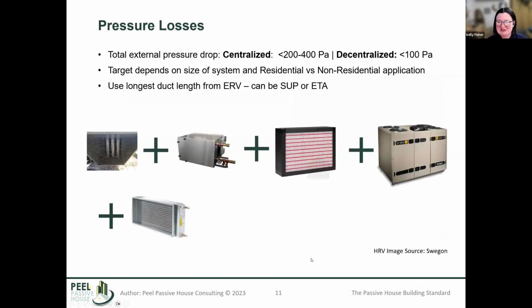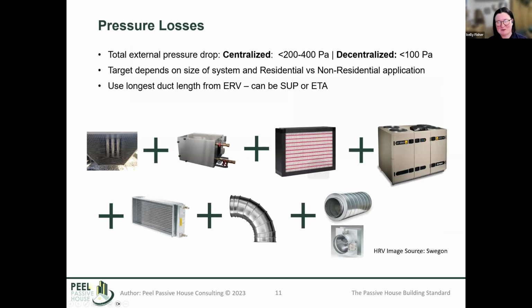I didn't realize this one had animation, so we just get everything up here. So the pressure losses are something we have to consider for multifamily buildings that we don't necessarily have to do for single family homes for Passive House certification. Every component along the way, whether it's an elbow or a silencer or a cooling coil or filters, incurs different losses through the duct network system. Making sure that we account for those on the longest duct run in the building, and weighing that against what our machines can provide, is very important in design. And then following through to make sure that all those components exist and are included in your project as specified is very important as well, so that you don't incur additional losses.